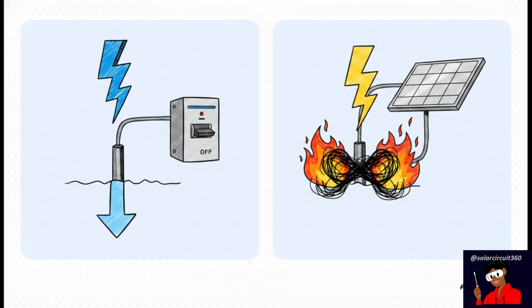On one side, you've got a low-resistance ground. Think of this like a multi-lane expressway. It allows a massive spike in fault current to flow instantly. And that high current is exactly what you want, because it forces your breakers or fuses to trip and shuts down the danger immediately. But on the other side, a high-resistance ground is essentially a traffic jam. It limits the current just enough so the breaker never trips. That electrical energy has nowhere to go, turns into heat, and boom, you've got a massive persistent fire risk.